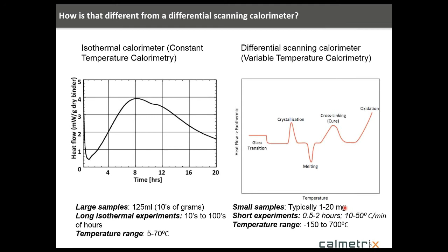As opposed to DSCs, where we use very small sample sizes, typically in the order of 1 to 20 milligrams. The experiments are very short because the sample size and the mass of the system is small. We can change temperature very rapidly, which helps give additional sensitivity when we're using very small sample sizes. So these are very short experiments, 30 minutes to a couple hours long. But we're usually interested in a much broader temperature range, say minus 150 to even greater than 700 degrees C.